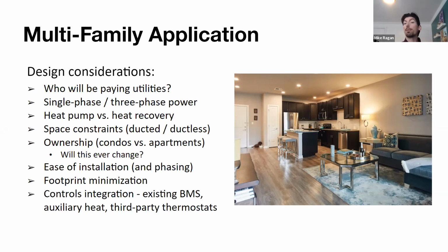Another question we'd have: what type of power do we have? Single phase or three-phase power? If we have single phase power, we need to look at mini split, multi-split, or single phase VRF as our only options. We don't have commercial grade three-phase VRF available. So we would be specifically looking at mini splits, one-to-one systems, multi-splits for a maximum of about 8 fan coils attached, or single phase VRF, which has, if I'm not mistaken, about 12 fan coils as the maximum you can connect. With three-phase equipment, you're talking about a much, much more robust system where you could have dozens of fan coils all attached to one single condenser unit.